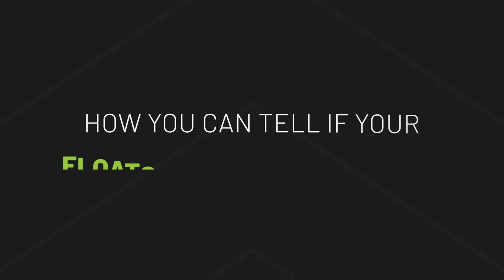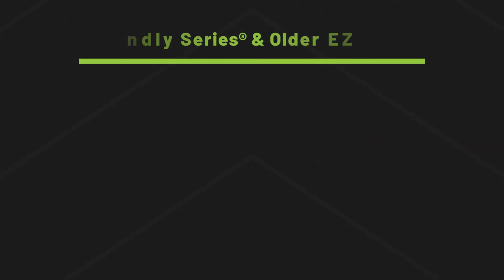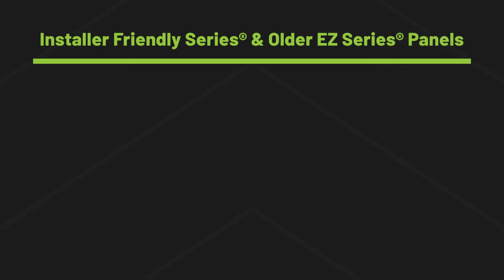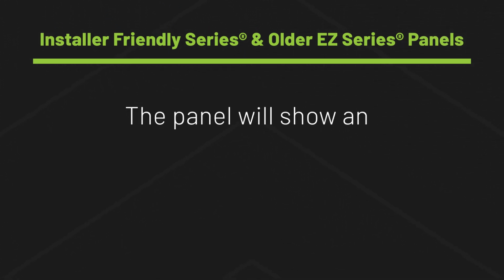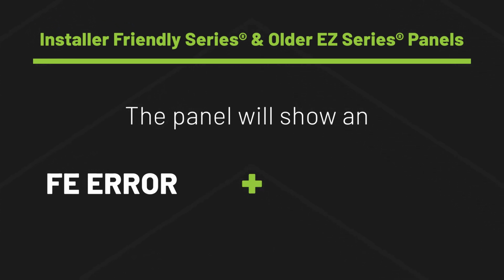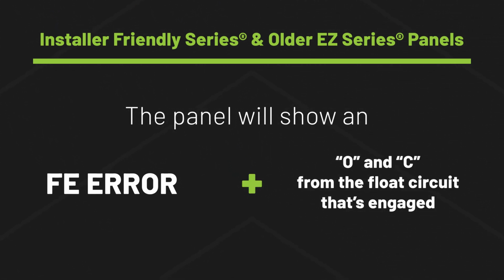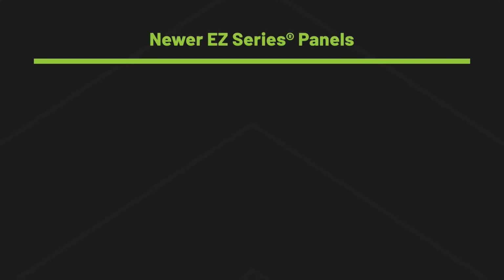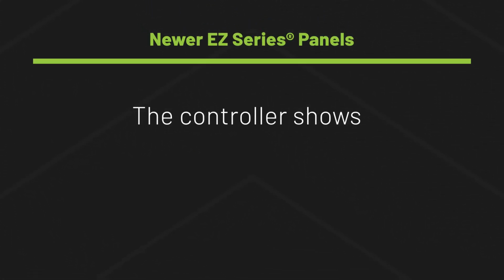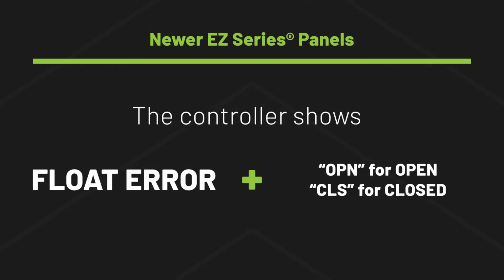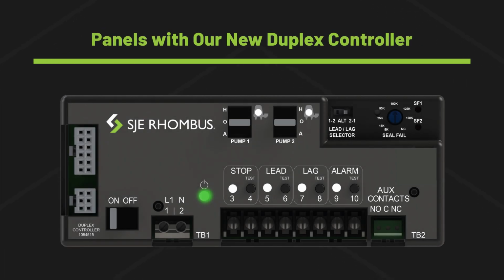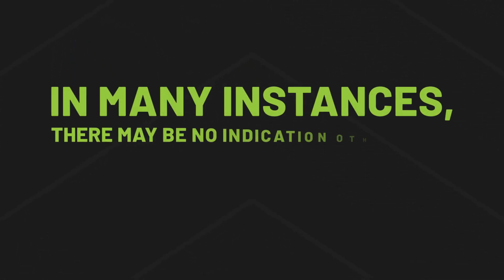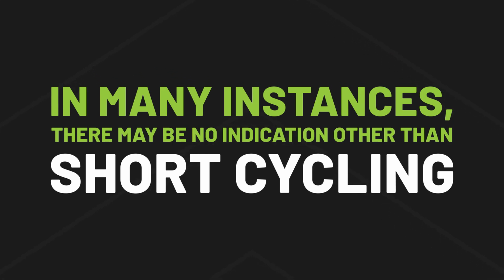How can you tell if your floats are out of sequence? In our installer-friendly series and older versions of the EZ series panels, the panel will show an FE error and a combination of O and C from the float circuits that are engaged. In newer EZ series panels, the controller shows float error with abbreviations OPN for open and CLS for closed. In panels with our newest duplex controller, an indicator light will come on when the floats are out of sequence. However, in many instances, there may be no indication other than short cycling.